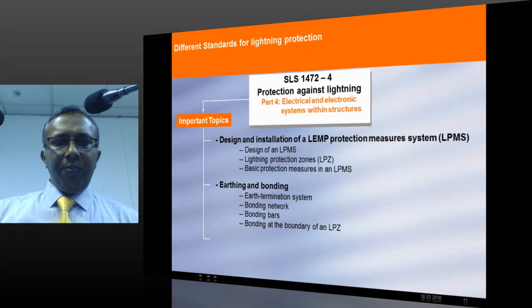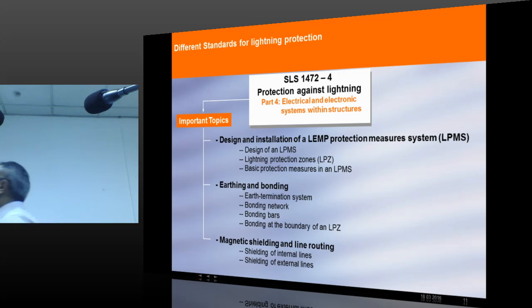Part number 4. Part number 4 talks about the design and installation of LEMP protection measures system. You know, LEMP, lightning electromagnetic pulse. It is becoming a very important subject when we talk about protecting sensitive electronics. Lightning electromagnetic pulse can directly kill sensitive equipment. It can make trouble for all the electrical systems. So in this particular part 4, the standard explains how the LPMS, the lightning electromagnetic pulse protection system, is designed.